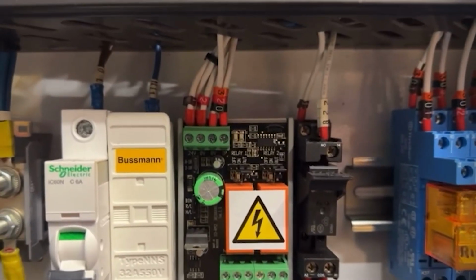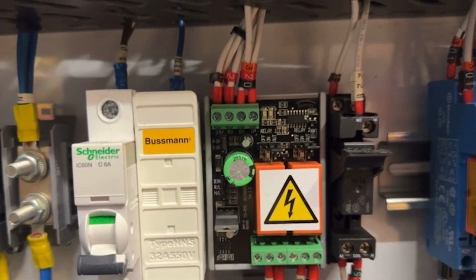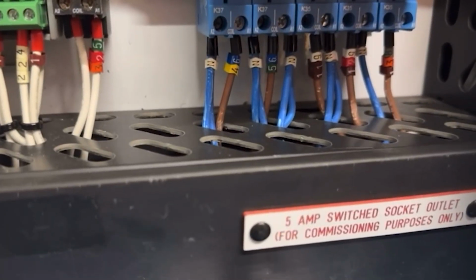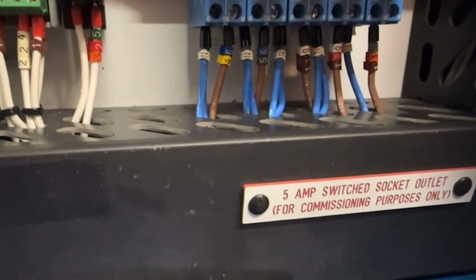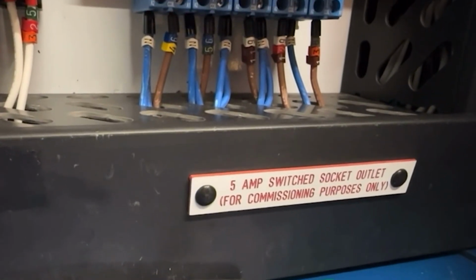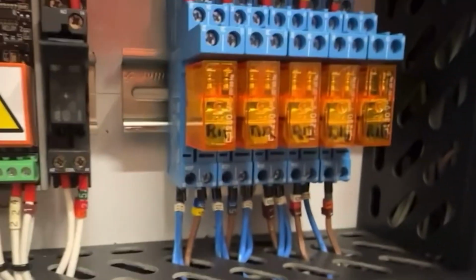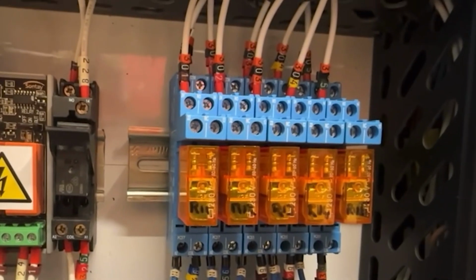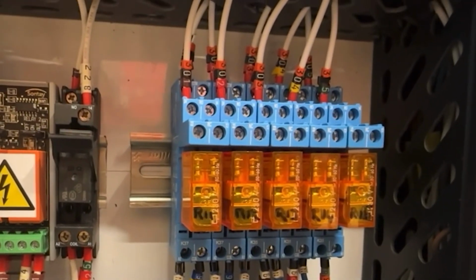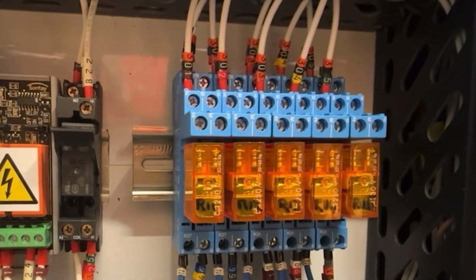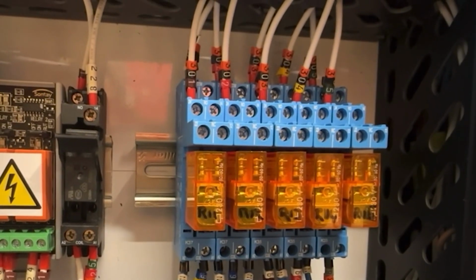Next to it, we've got another one of those cards that I suspect works on some sort of bus system, and a relay. And there we've got a load of 5 amps. Oh, look, interesting. That says 5 amp switch socket outlet for commissioning purposes only. I'll give you a clue. That is not a 5 amp switch socket outlet. That is a bank of relays. So clearly, the panel has been modified at some point in its career to incorporate those.